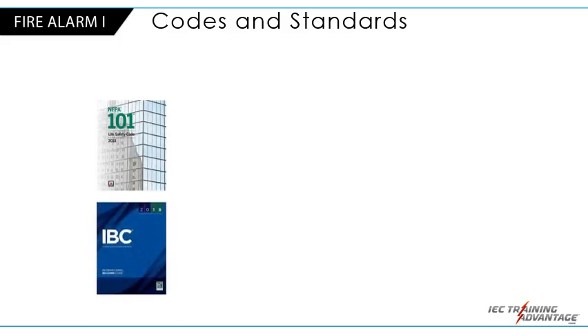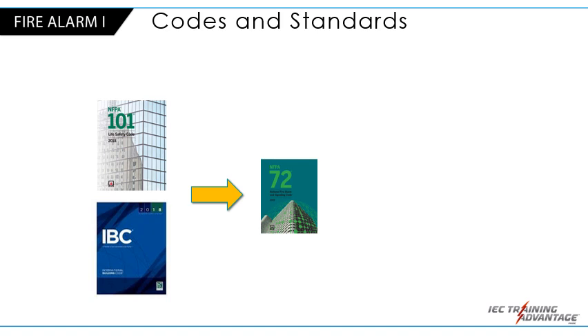So codes, like Life Safety 101 and the International Building Code, require a type of system. They'll look to NFPA 72 for most standards on how that system is to perform. NFPA 72 looks to product standards to specify how products operate and to ensure they are safe. For example, they'll look to UL listing, or Underwriters Laboratories, to ensure that the products that comprise the fire alarm system are listed. NFPA 72 requires all products used to be listed. This implies that they meet some recognized product standard.